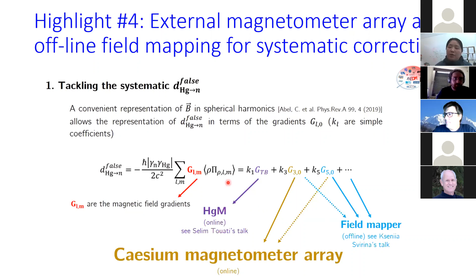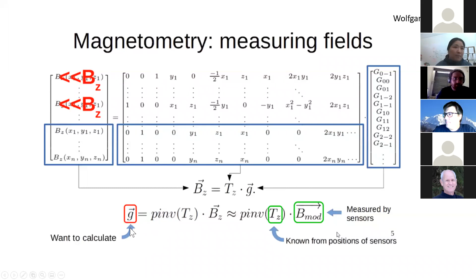So those optically pumped magnetometer cells can be fabricated in large numbers and then put in arrays. There was discussion about what configuration to put them in to give us the best handle, because after all, the gradient is what we're trying to measure. But when you do the measurement, you have magnetometers placed at different positions in space. Now you have to know your response function matrix very well, and invert it based on what you measure from the field sensors, to get what you need for the EDM correction.